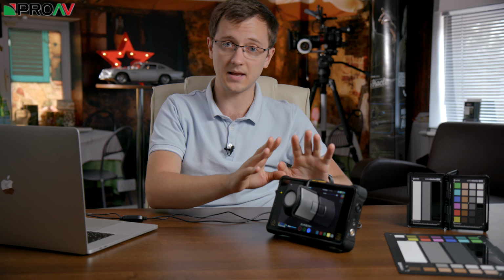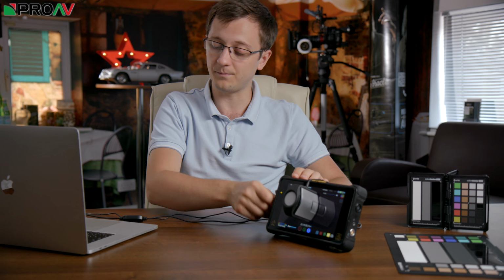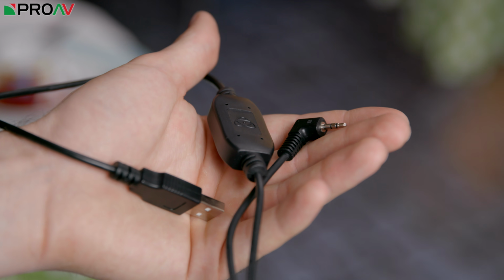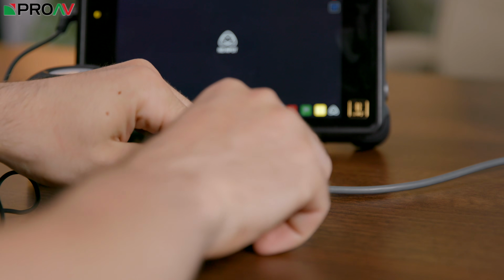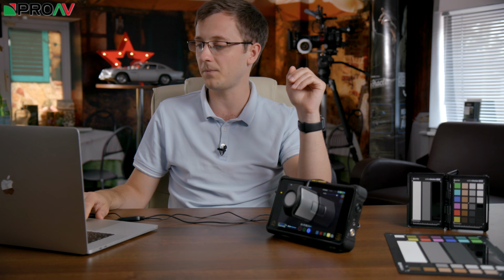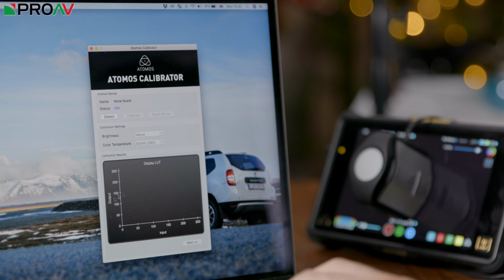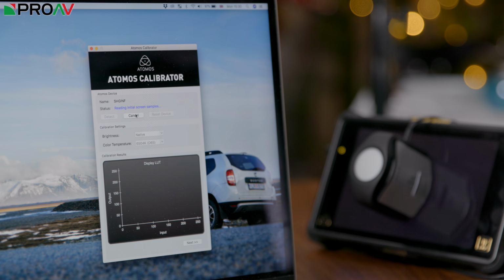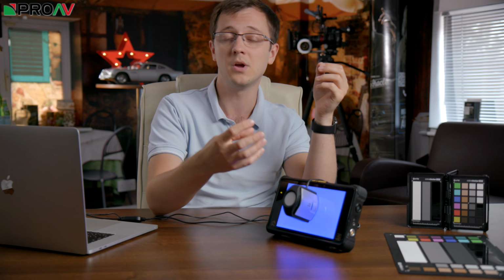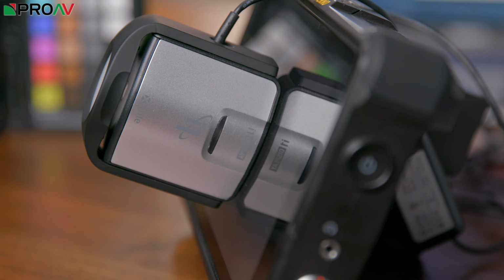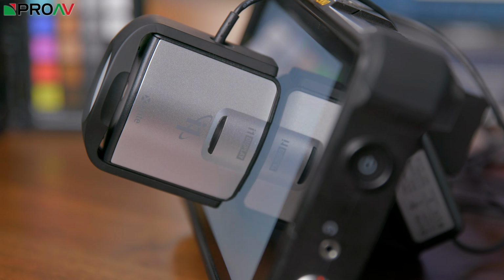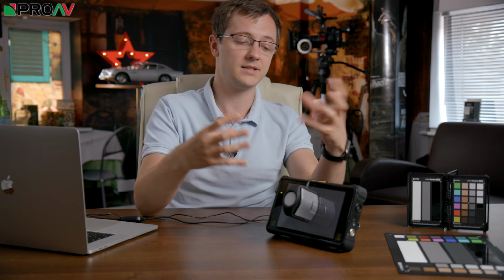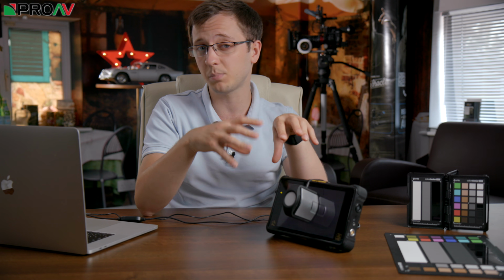You then have to connect the Atomos to your computer with the special cable that Atomos sell, the USB to LANC sync cable, and you of course connect the probe to your computer as well. Then once both of them are connected, you open up Atomos's software. You can detect the Atomos device and then simply press calibrate. What it's going to do is bring up a reference pattern on here, and it's just going to start flashing colors at the probe. The probe is then going to measure those colors that are coming out of the screen, and it's going to adjust and create a profile to get those colors as accurate as possible.